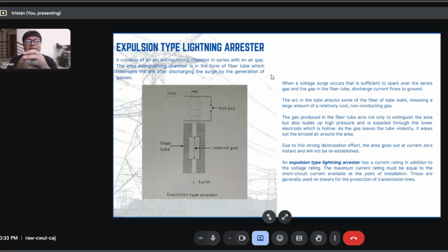So ang expulsion type lightning arrestor has a current rating in addition to the voltage rating. The maximum current rating must be equal to the short circuit current available at the point of installation. So these are generally used on towers for the protection of transmission lines.